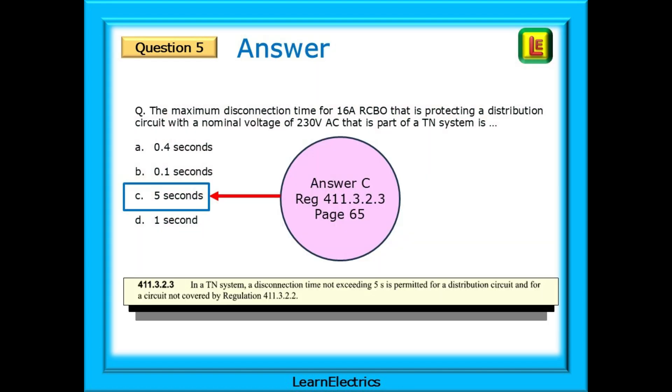The answer is C, 5 seconds. The answer is given in regulation 411.3.2.3, on page 65. Look at the index on page 583 for disconnection times distribution circuits. It will direct you straight to regulation 411.3.2.3.